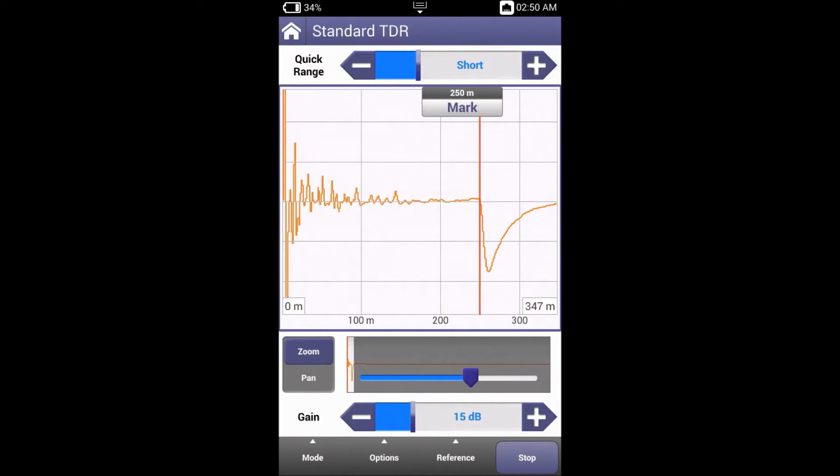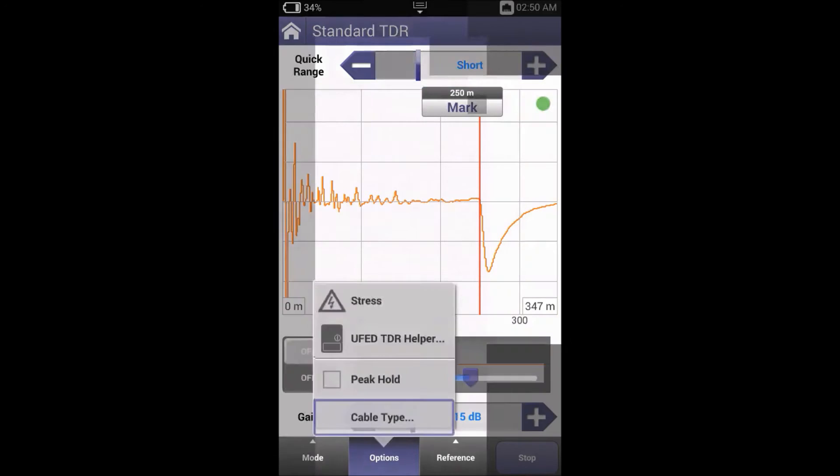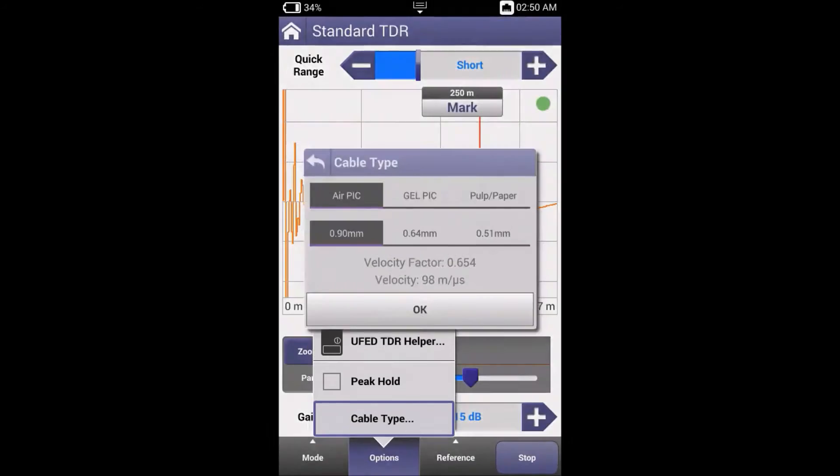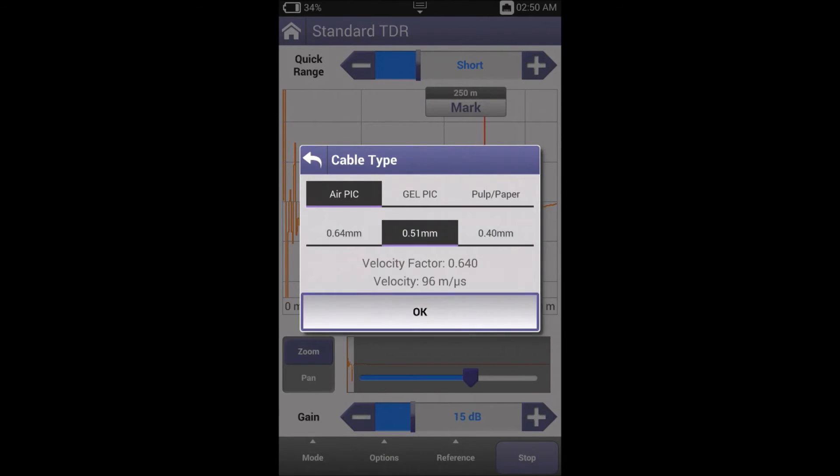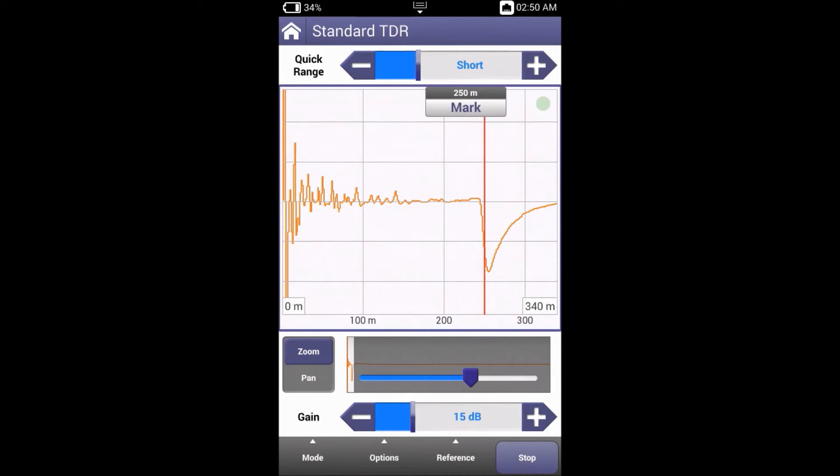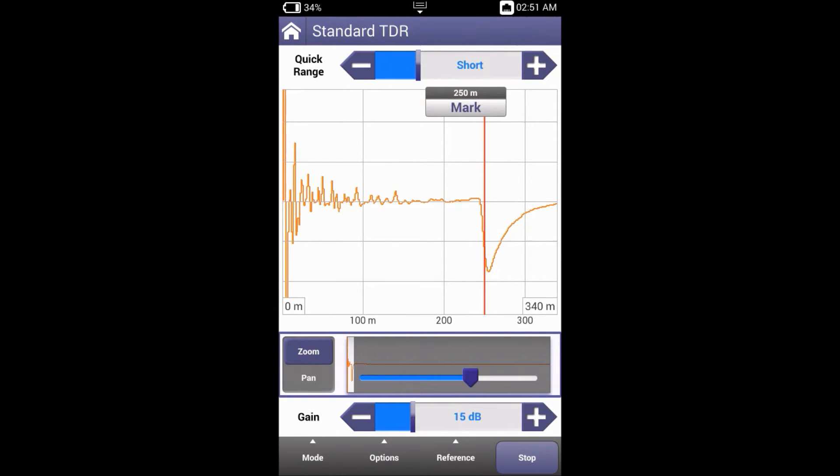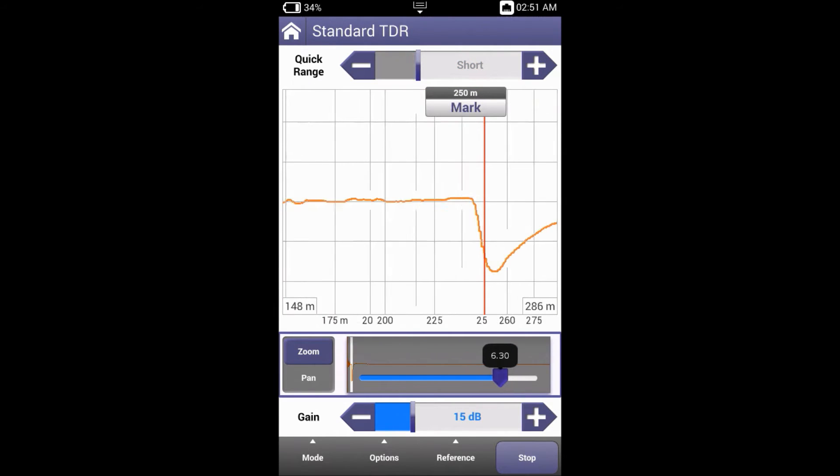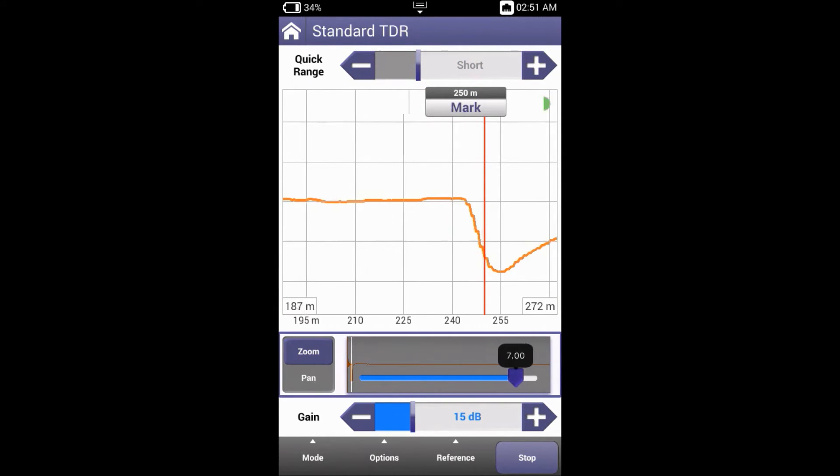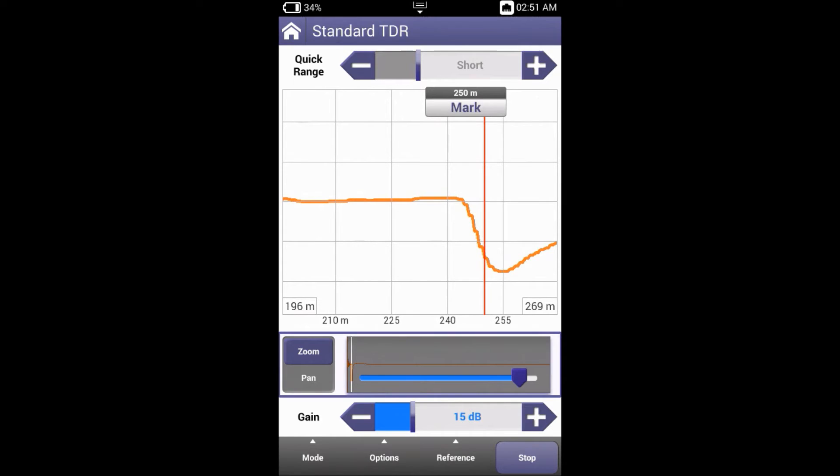Now increasing the quick range, we'll find the short that we saw earlier. Currently it says about 250 meters. Let's go back to options and change the gauge. We can see that there's a difference in where the dip begins.